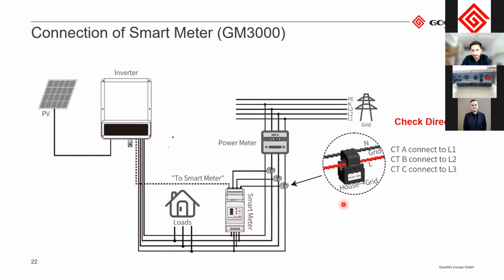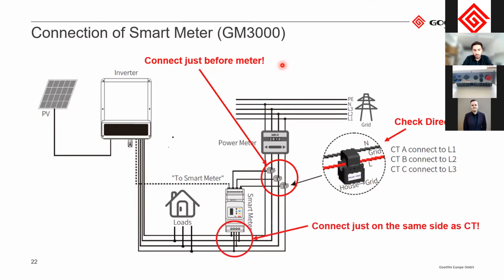And please, when you connect the CTs, check the direction. Each CT goes to each line, so line 1, 2, and 3, and make sure that it goes from the loads towards the grid. So it says K to L. So K is then the loads, and L will be the line or the grid. And they should be connected just before the power meter, before entering the grid connection. Exactly. Connect just before the meter and check the direction. Those are the most important things.